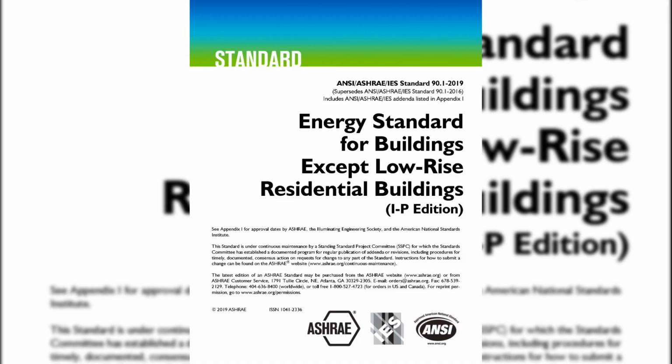15. Design and load calculations. Similar to heating, calculations are based on the net floor area. 16. Design conditions. A. Inside, 78 degrees Fahrenheit DB. B. Outside, 89 degrees Fahrenheit DB, max. C. Cooling tower, 78 degrees Fahrenheit WB, if used. D. VAV case, standard. E. Carbon dioxide sensors reset minimum central OA per paragraph 8.3.